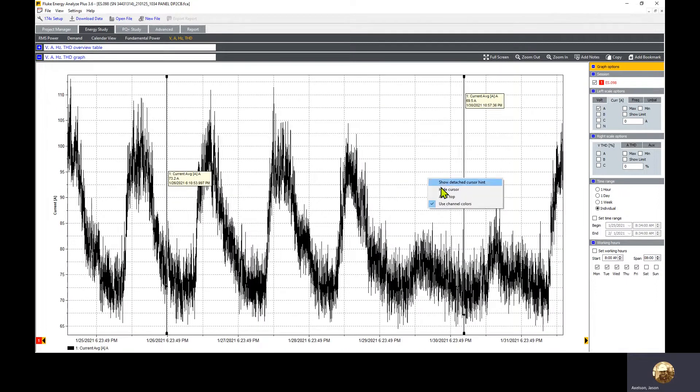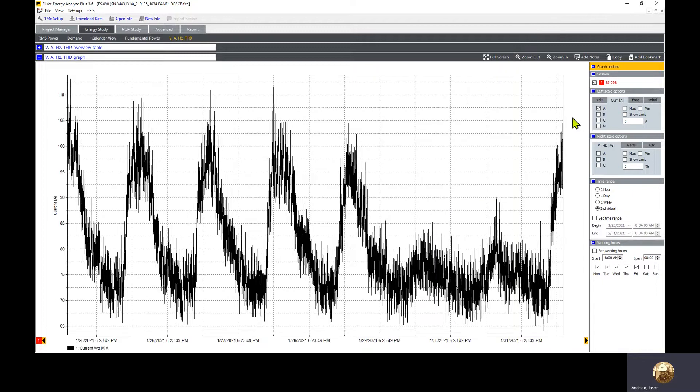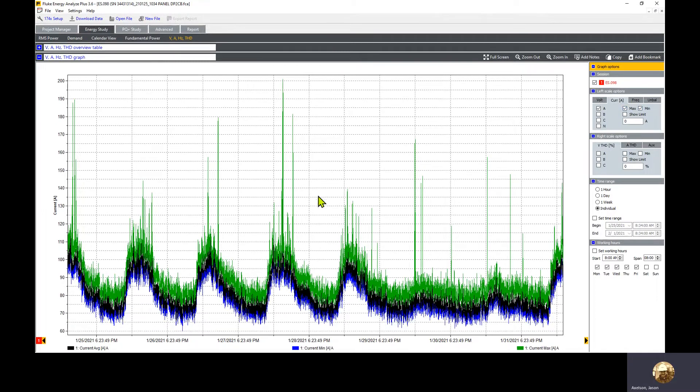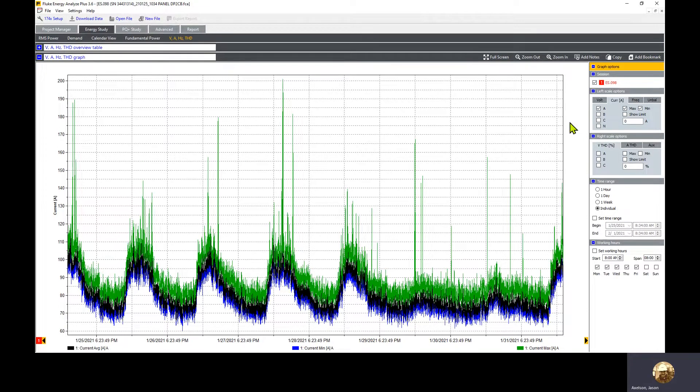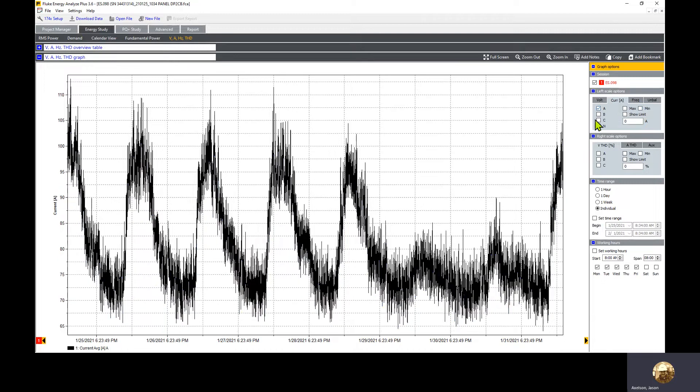I'm going to hide the cursors to make it look cleaner. Min and max can be added, but these can skew the numbers because these are the min and max half cycle measurements during the period. We really want to look at averages, so we want to hide those. We'll start with the A phase only.